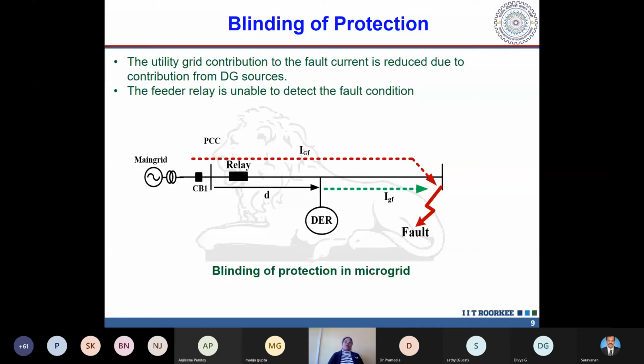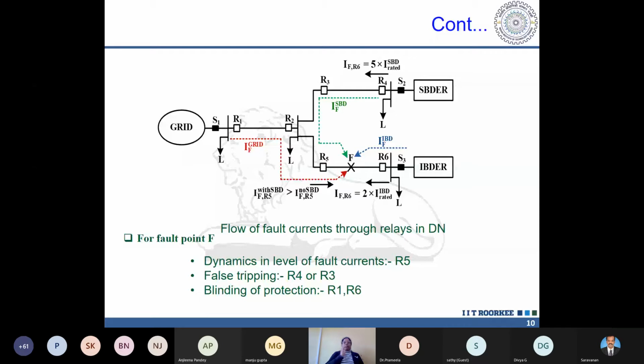These are the concepts I'm sharing with all of you. We have reviewed many papers, and I'm presenting them in front of you. So these are the 4 or 5 concepts, because the 5th one I told you is that if the fault is incepted in front of the inverter based renewable source, then our thing will be different. The current magnitude will be 2 per unit. It will be clamped automatically with the help of the inverters. But if the fault is created in front of the synchronous based renewable source, then it is going to be many-fold more.